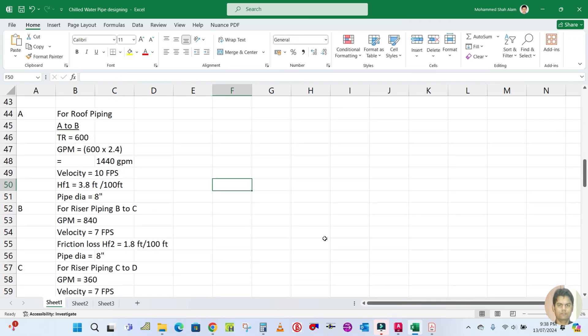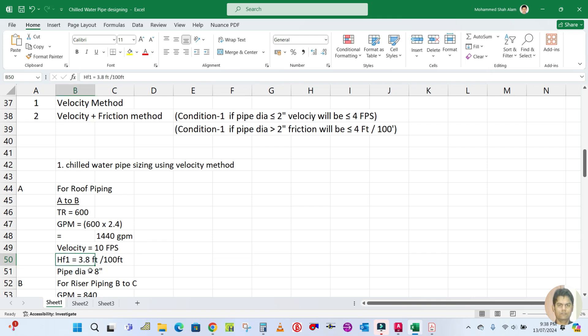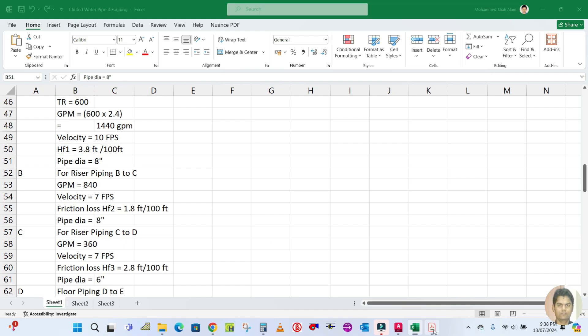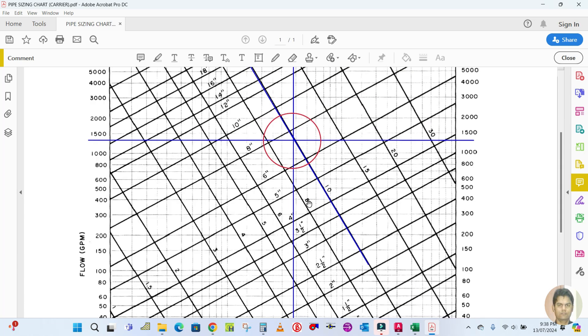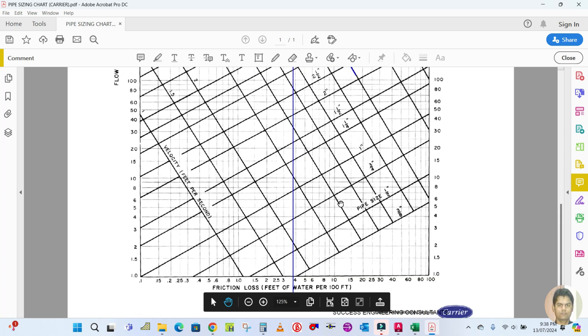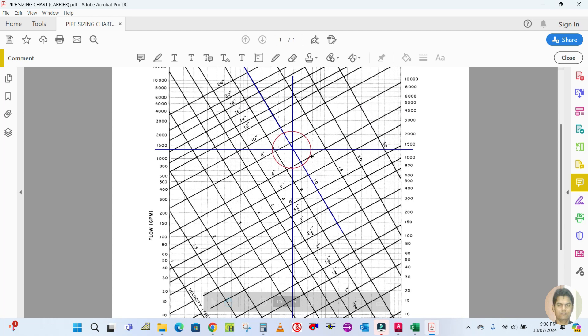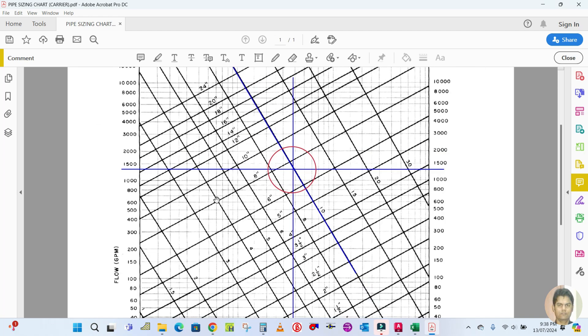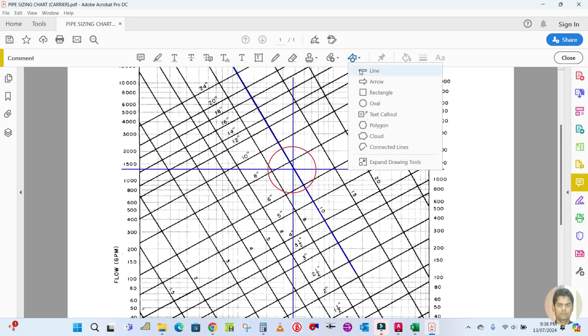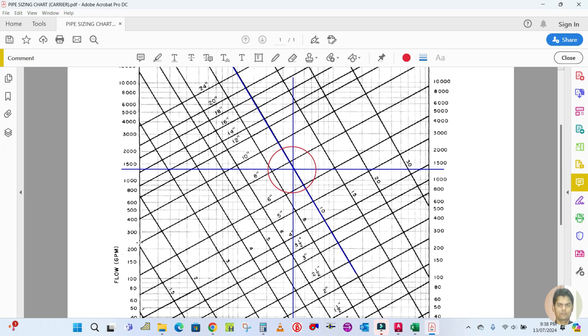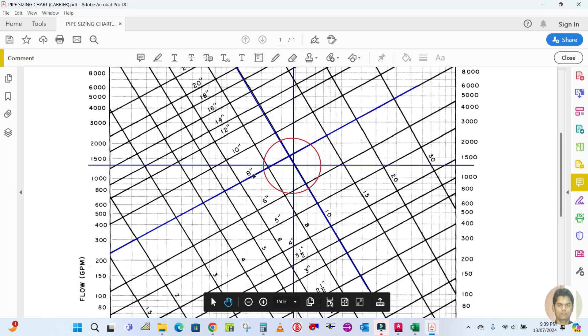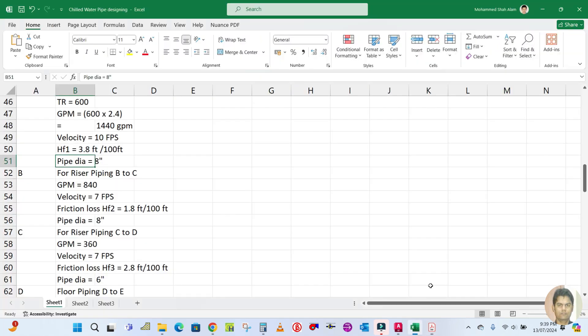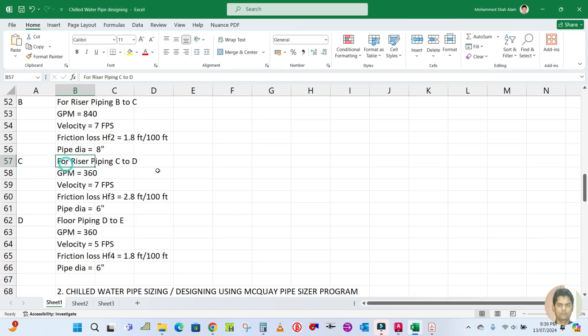So the friction loss HF1 is approximately 3.8 feet of water per 100 feet. For the pipe size, the intersection point falls nearest to the 8-inch pipe size line on the chart. Therefore, the pipe size for roof piping A to B is 8 inches.